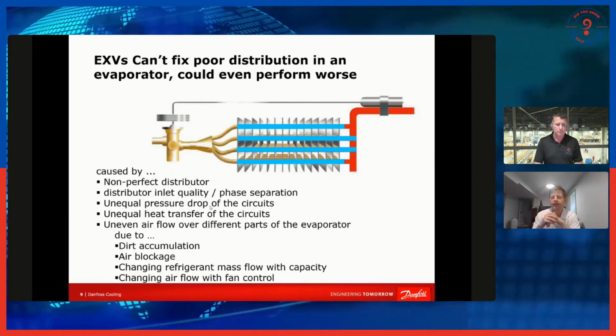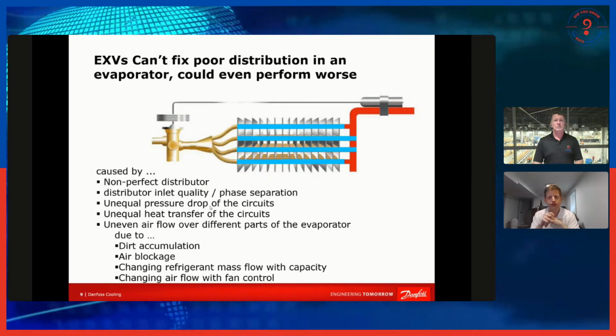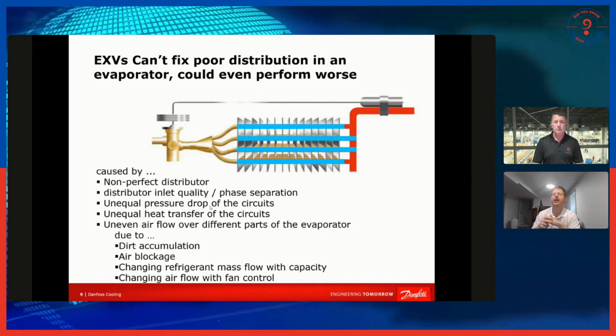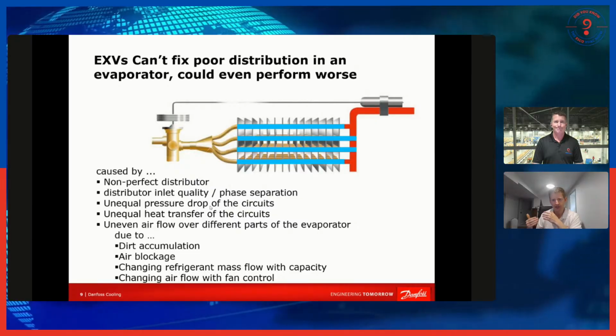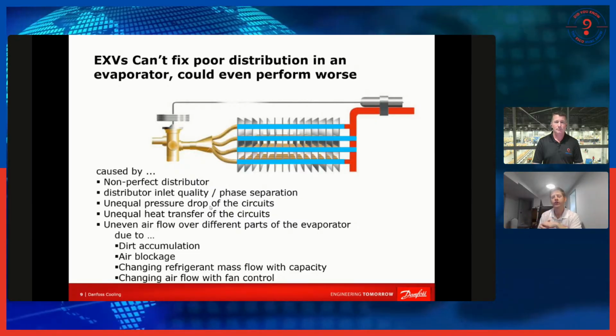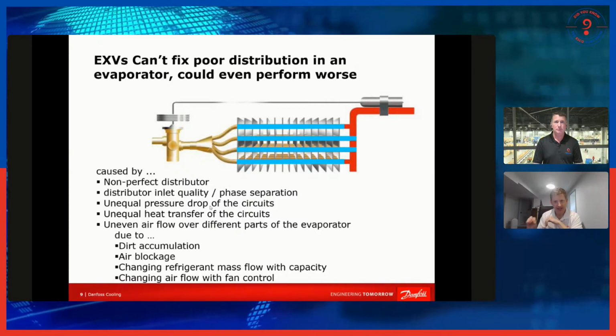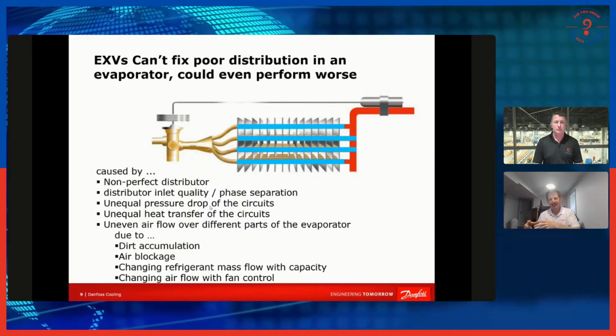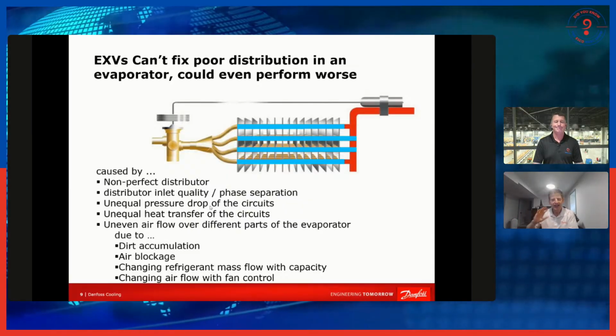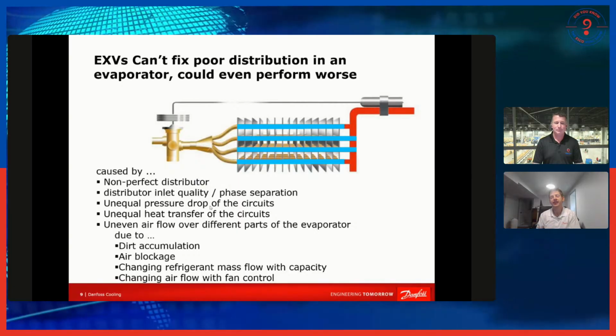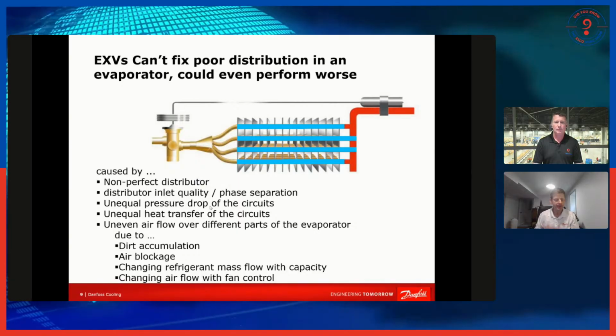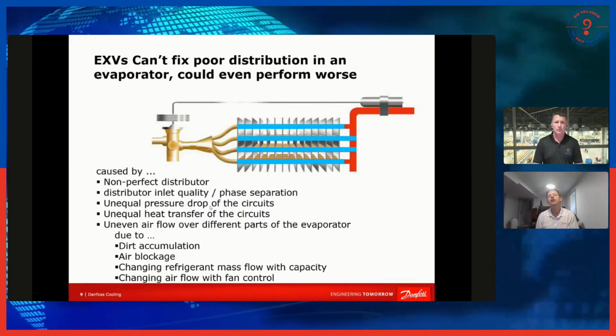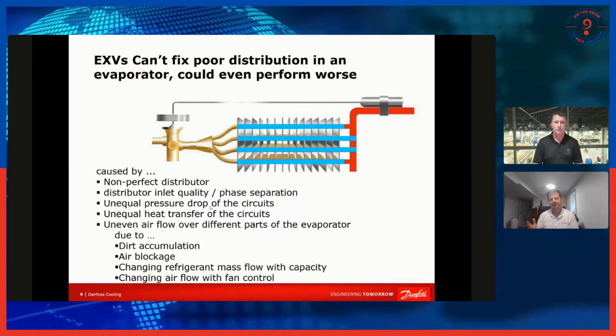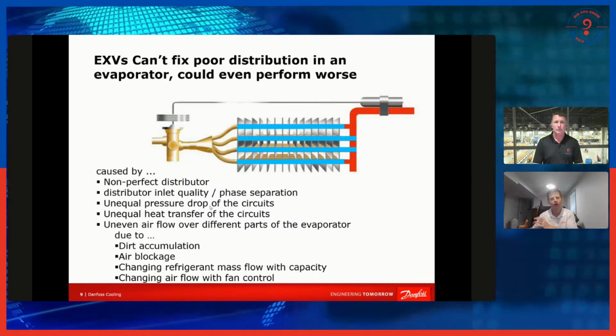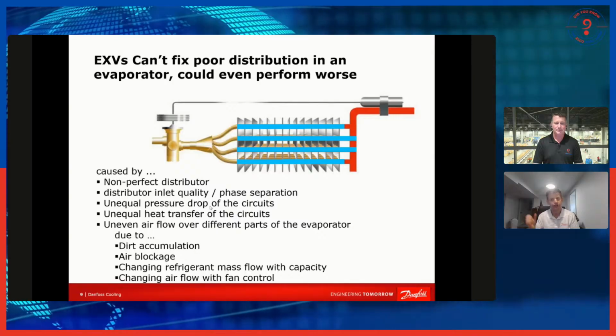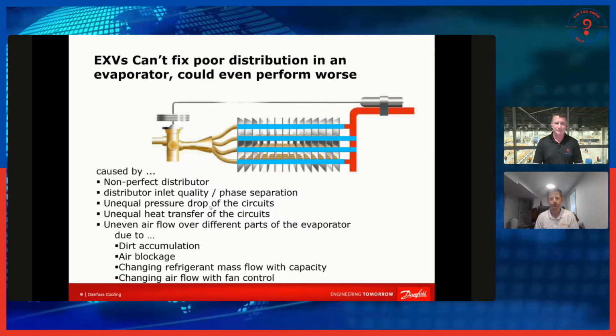Yeah, and this is one of the examples where an EXV could actually perform worse. If you have poor airflow, if you have an air filter that starts to get blocked up and you really restrict that airflow, an EXV could perform worse because it's digital, it's getting an exact measurement. Whereas the TXV kind of takes time to heat up and cool down. It's kind of doing its own thing, and then it eventually starts reacting. So I've seen situations where installation of EXVs has led to worse performance because it is precise, and TXVs kind of slough along through some hunting, and the EXV reacts quickly, and it restricts too much as a result. So, yeah.